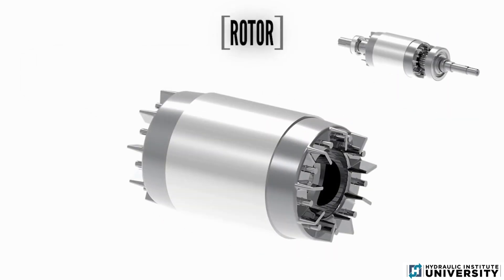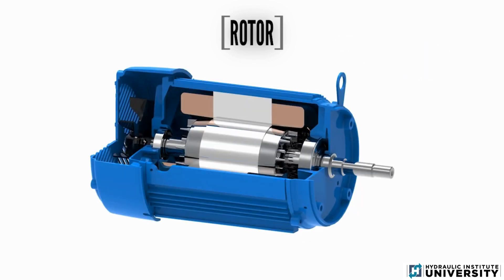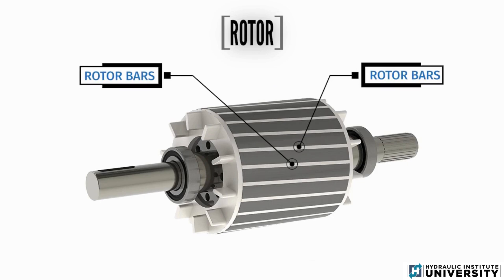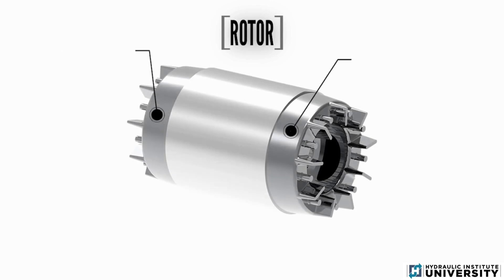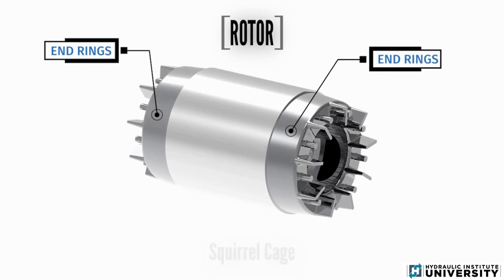The rotor is the rotating part within the electric motor. It consists of another set of ferrous laminations mounted on a shaft; the laminations have slots to hold the electric conductor bars — rotor bars. The rotor bars act as a closed conductor short-circuited at each end by end rings. This type of rotor is often referred to as the squirrel cage.